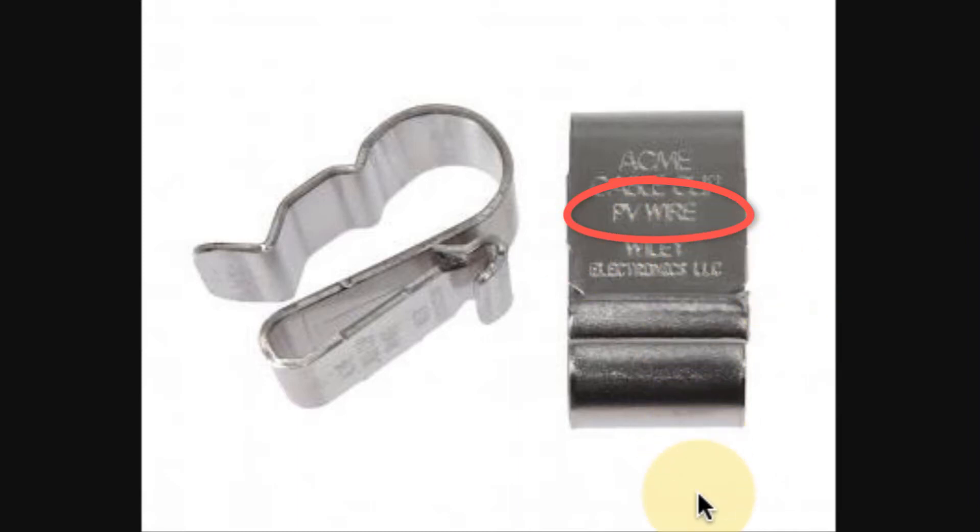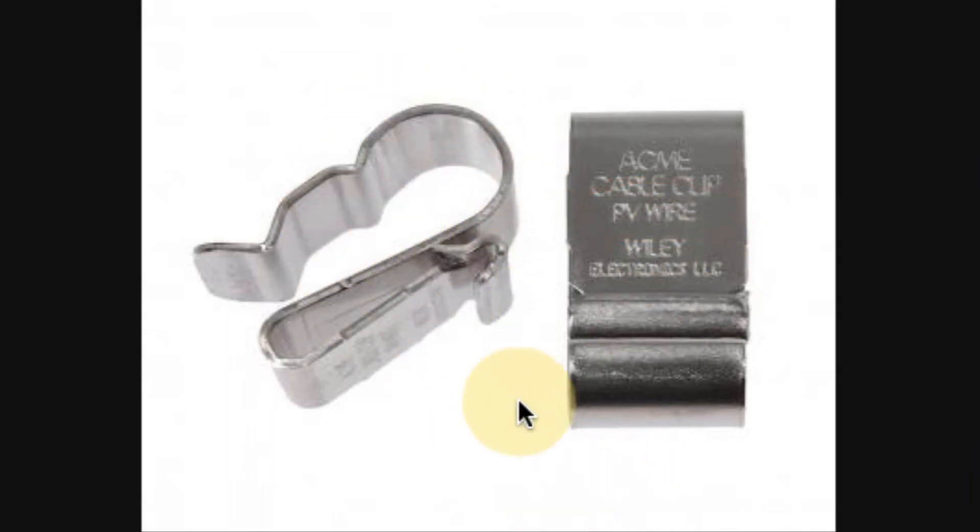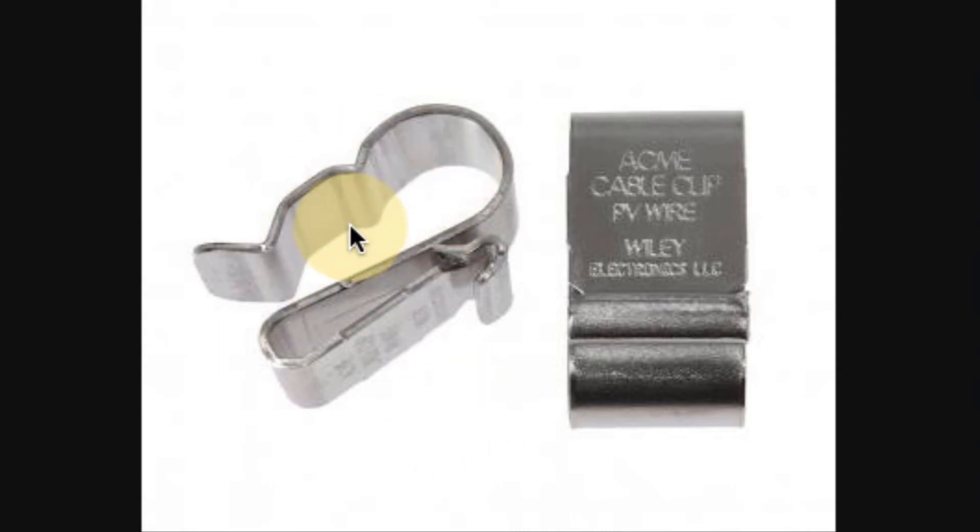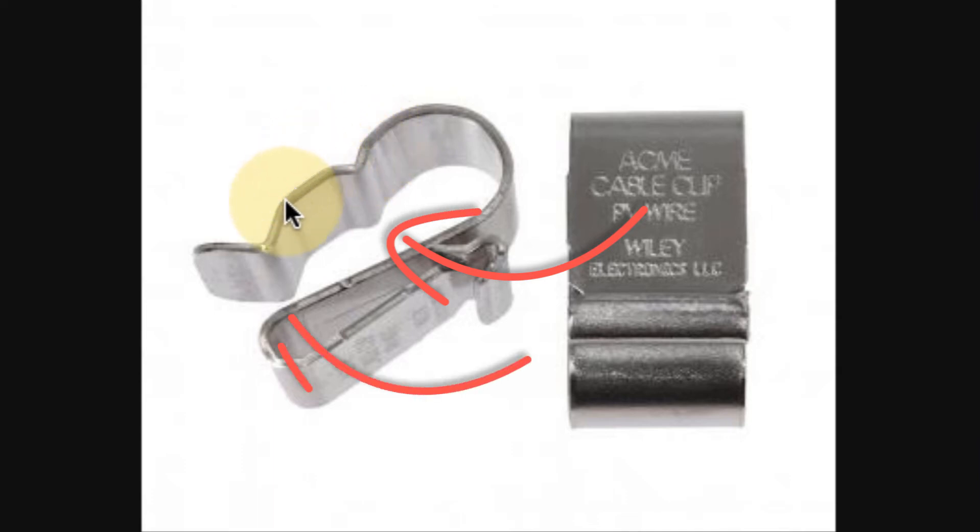There's a size that doesn't say this and there's a size that does say PV wire. And that's because the diameter that's built into the clip is much bigger, big enough to hold solar wire quite nicely. There's a smaller clip down here, nicely clip onto USE-2 or you could slip in two solar wires and it would still grab it. I also want to show, besides the barbed structure that he has here, that he's got these nice bends that go down like that.